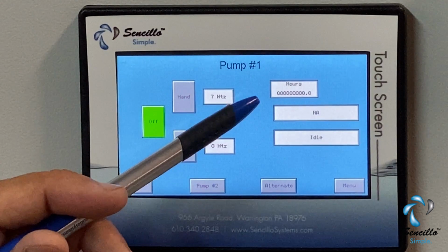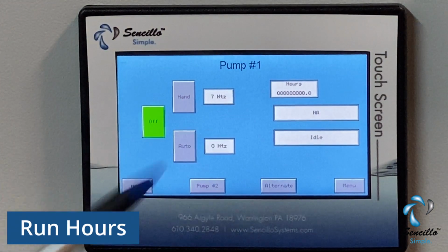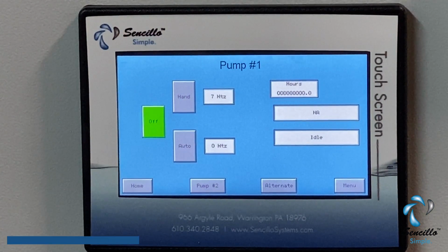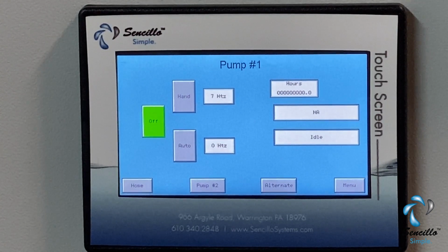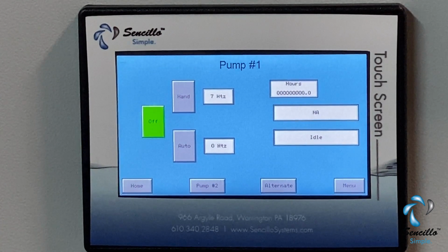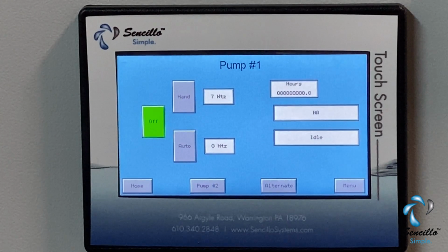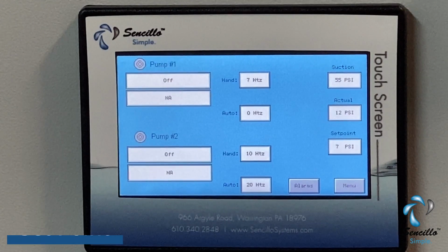Let's talk about run hours. This indicator will keep track of the number of hours that the pump has been running. Each pump has its own indicator, and as a PM maintenance, you might want to keep track of the hours to make sure that they're close to each other, indicating that the system is alternating fine and the pumps are running well. Let's talk about your set point.